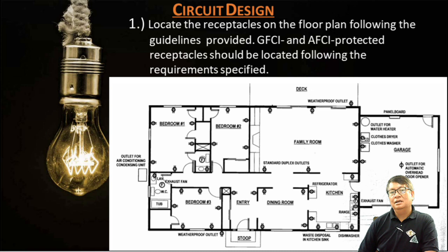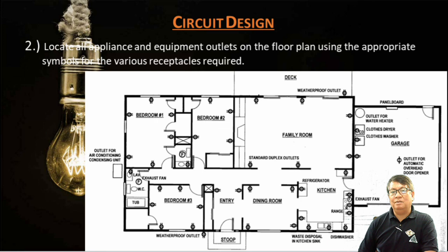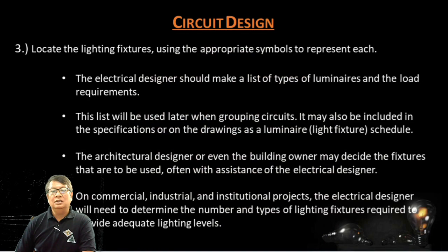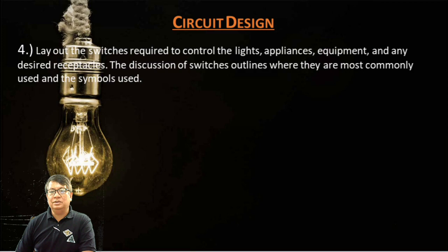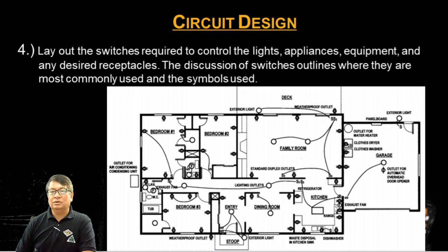Okay, balik lang tayo ng konti. Unang-una, locate the receptacle on the floor plan following the guidelines provided. GFCI protected receptacles should be located following the requirements. Yung pangalawa, locate all appliance and equipment outlets on the floor plan using the appropriate symbols of the various equipment. Third, locate the lighting fixtures using the appropriate symbols to represent each. Then lay out the switches required to control the lighting, appliances, and equipment.